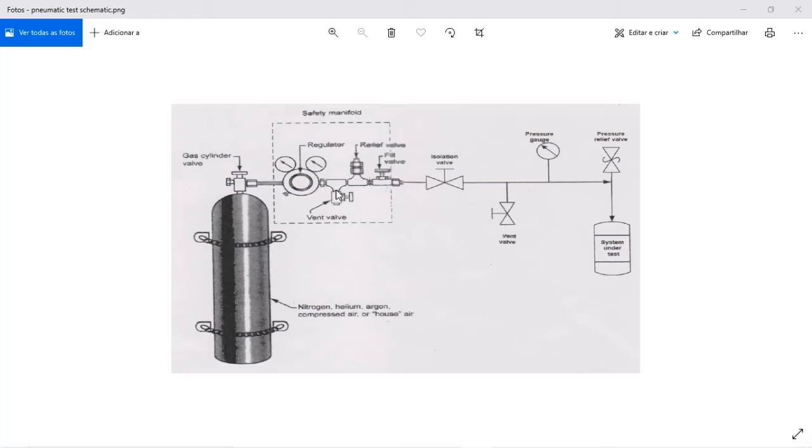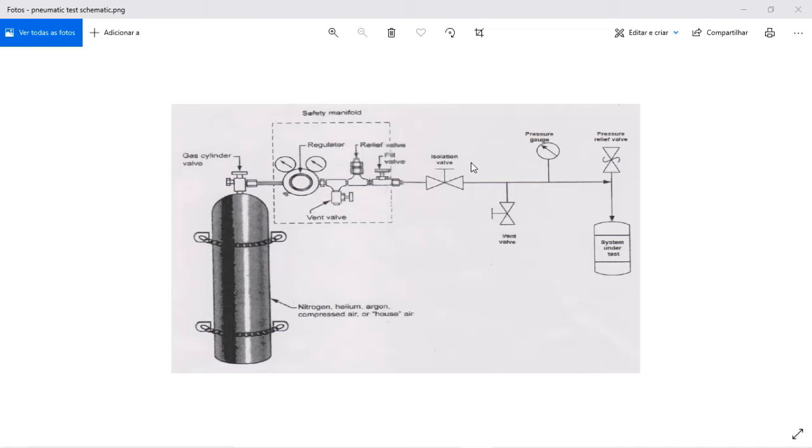Most often we have a vent valve, we have a relief valve, and we have a fill valve to connect the cylinder to the system. Of course you must consider having the system isolation valve because you will use that to connect and disconnect the cylinder safely.